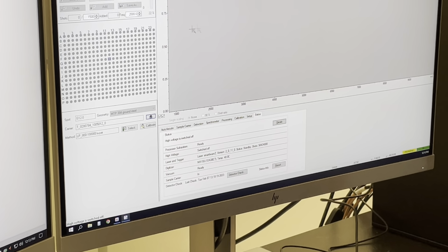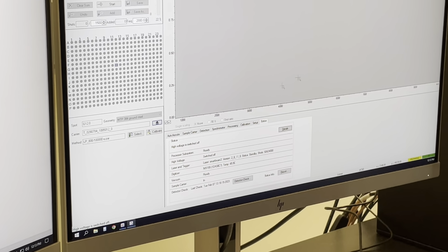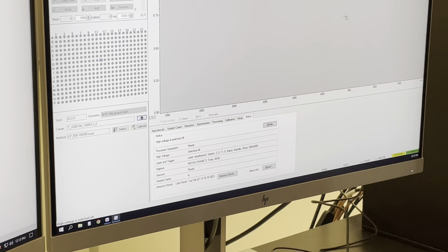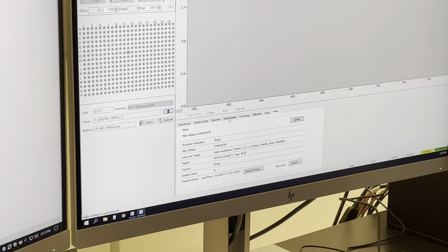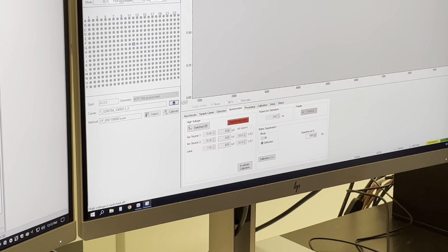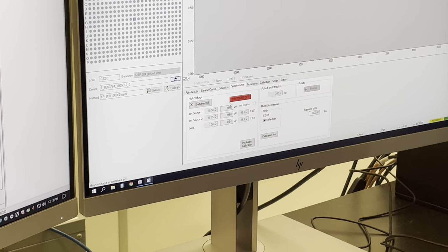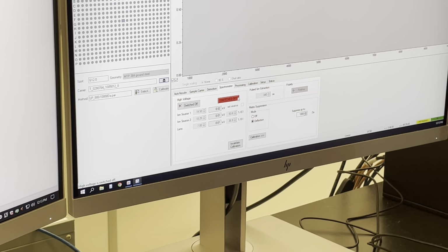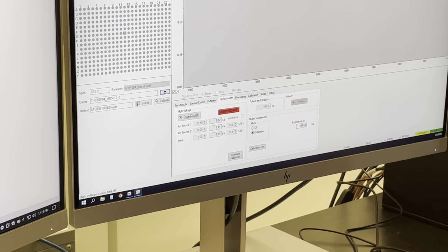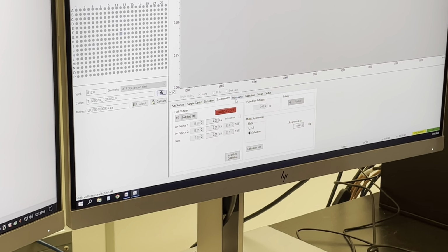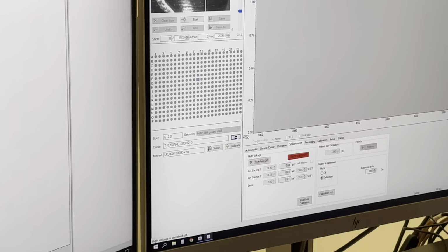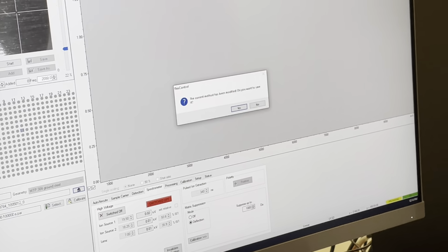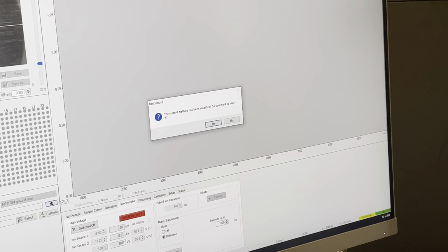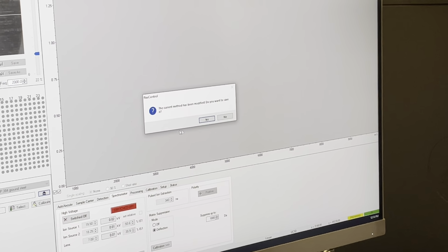Okay, so this is the window that is going to show us the real-time mass spec data from this screen. And we can go to spectrometer. Make sure the high voltage is off. Right now it's off, right? And then we are going to load our method. The method can be loaded through here, select method, or you can go to file, select method. Either way.